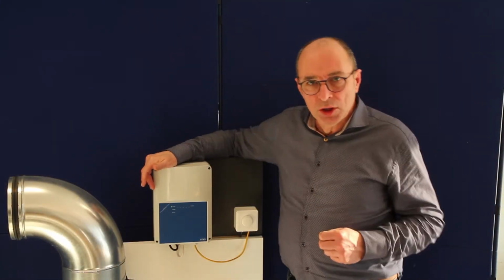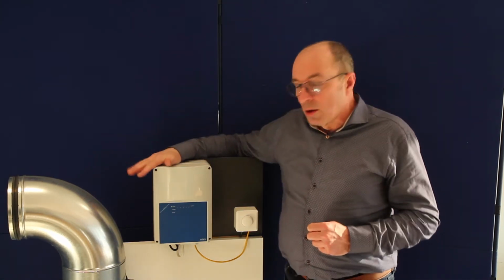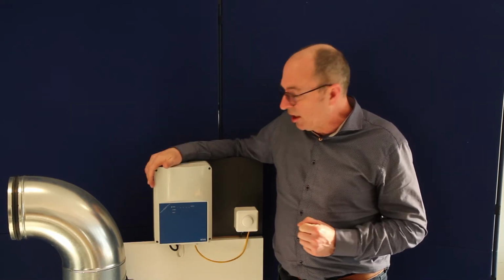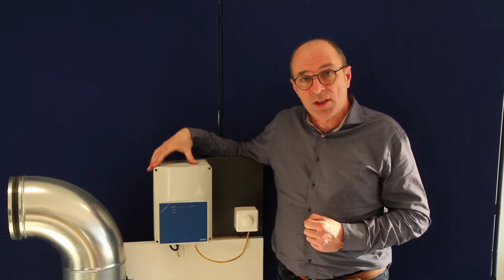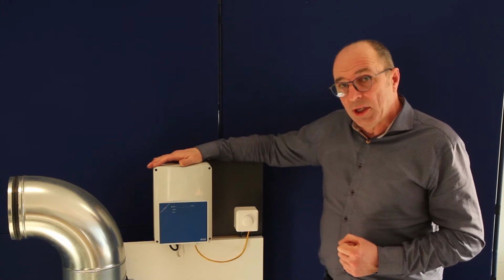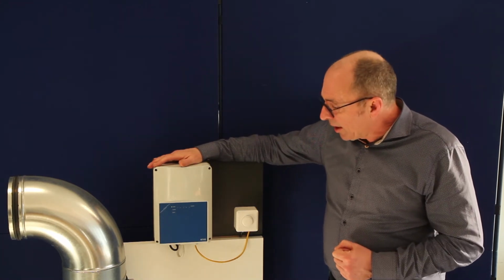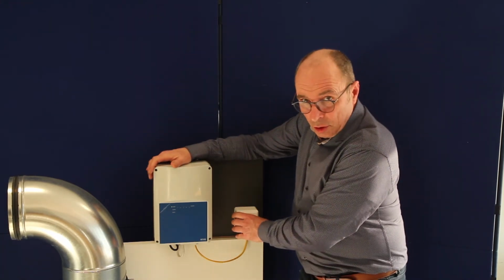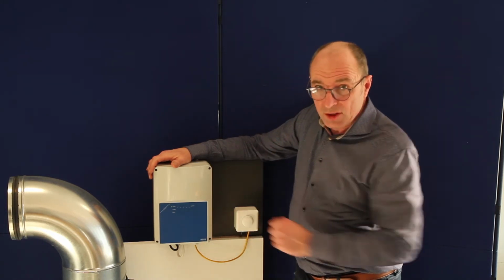I repeat briefly the two operating modes of the device. First, it can operate in a manual mode where you can select the speed between 1, 2, 3, 4, 5 in the Modbus registers via a computer or via a building management system. Or it can be operated in automatic mode, listening to the sensor or potentiometer on its slave input.